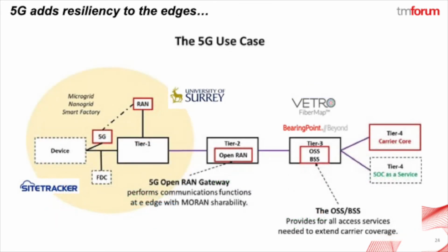mode. The resilient 5G use case for the smart grid overlays our now familiar four-tiered architecture as shown in this diagram. At the microgrid on Tier 1 on the left, the various devices are now connected to a fault-tolerant microgrid controller with wired Ethernet connections. For resiliency, the Tier 1 fractal also poses as a 5G picocell at that location, and each device also connects to the microgrid controller with a 5G wireless connection. Both connections use the DDS protocol supporting low latency, real-time, redundant communications for high availability.